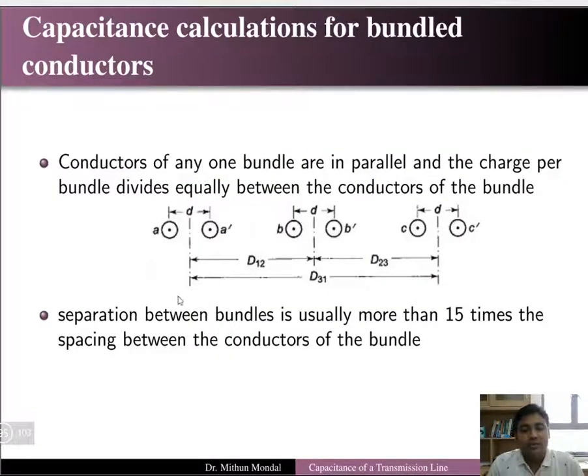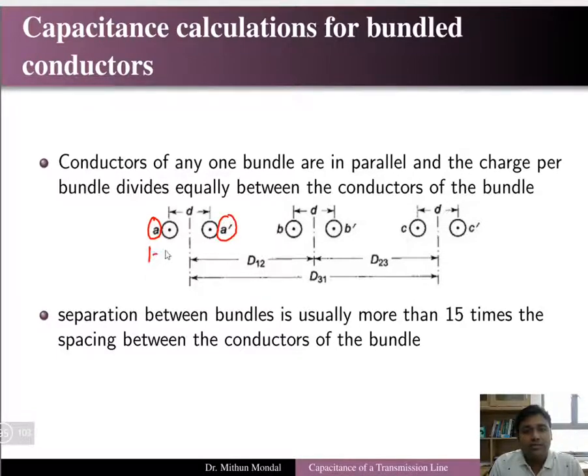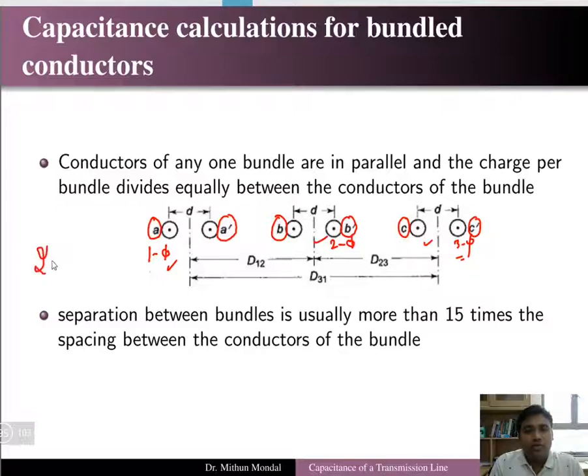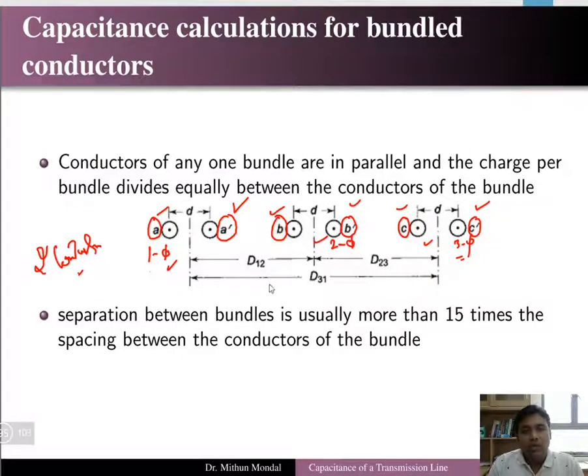Let us see a diagram where you have three-phase conductors and two conductors in each bundle. Conductors A and A' form one phase, conductors B and B' form the second phase, and conductors C and C' form the third phase. So A and A' form one bundle, B and B' form another, and C and C' form the third. The distance of separation between individual bundle conductors is small d.